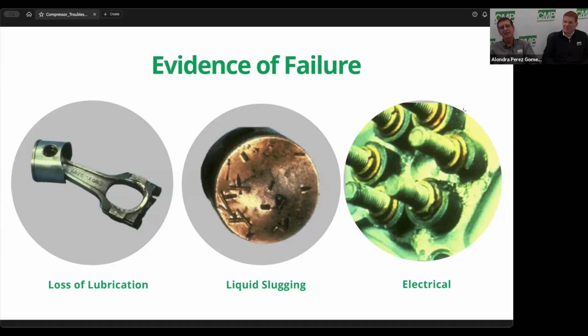Everybody's time was wasted if you don't take the time to find out why that compressor failed. Because like I said, 9 out of 10 compressors fail because something happens in the system, whether it be a contactor goes bad, and also the superheat. Expansion valves kind of have a lifespan on those too. Anytime you send vapor and liquid through an orifice, eventually it's going to cavitate that orifice and enlarge it. So expansion valves will need to be adjusted from time to time.